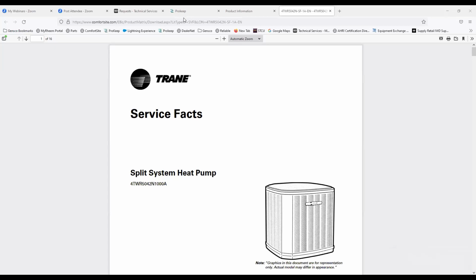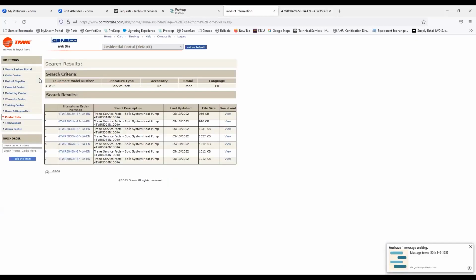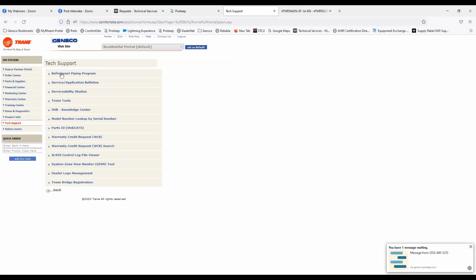So go back to product information. We're going to get back out of this. So all the information is right in there. Here's the tech support tab right there. So tech support, refrigerant piping program. And this is the same program that we've been using for years. Go to installation. Select the type of unit, heat pump or air conditioner. Select the family. This time we'll do a Silver 15, which is our American Standard 15 SEER.